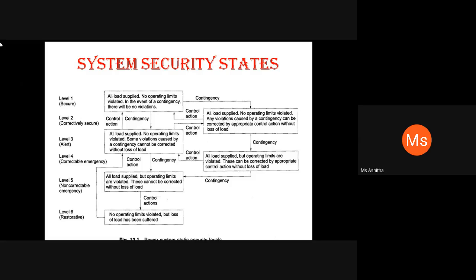Level 1 has an ideal security but is too conservative and costly. The power system survives any of the credible contingencies without relying on any post contingency corrective action. Level 2 is the most economical but depends upon post contingency corrective rescheduling. So level 1 is secure, level 2 is correctively secure, level 3 is alert, level 4 is correctable emergency, level 5 is non-correctable emergency, and level 6 is restorative. Once the system is restorative, it is given back to correctable emergency, and then from there it is given to the secure level, that is level 1.